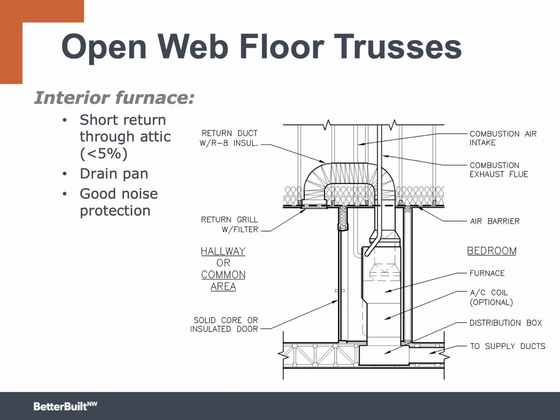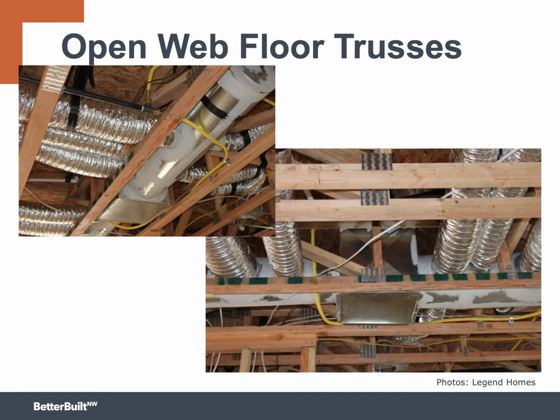In this situation, it's really a good idea to use that 5% of duct length exception allowance for a little bit of extra return that pops into the attic. It's a short loop and it muffles the sound. Seems to work out pretty well. Here you can see the base can from below. It attaches to that round trunk line. The base can is directly below the furnace up on the second floor.